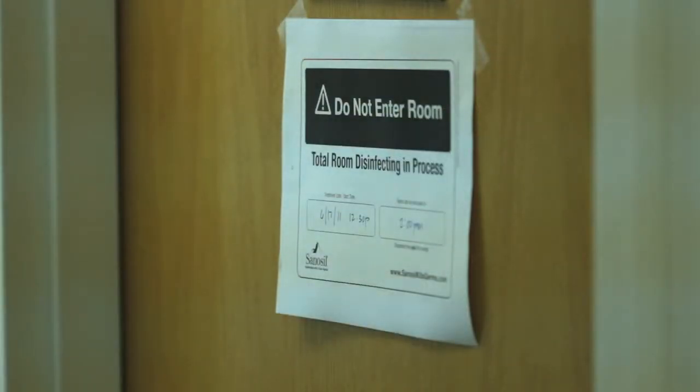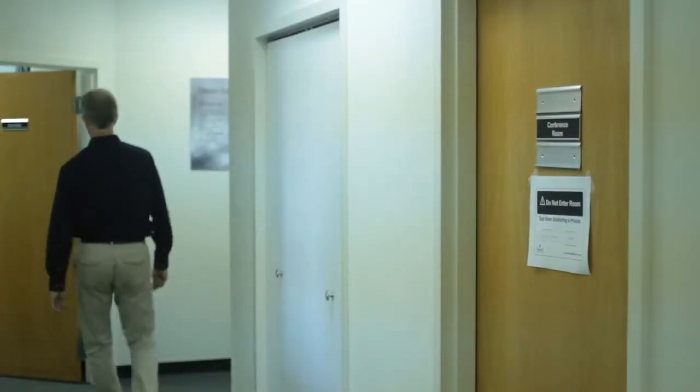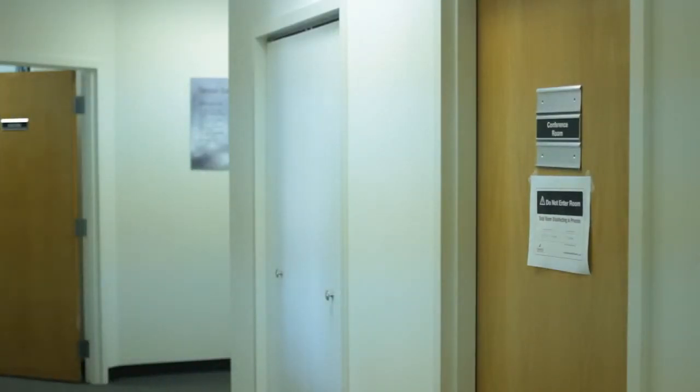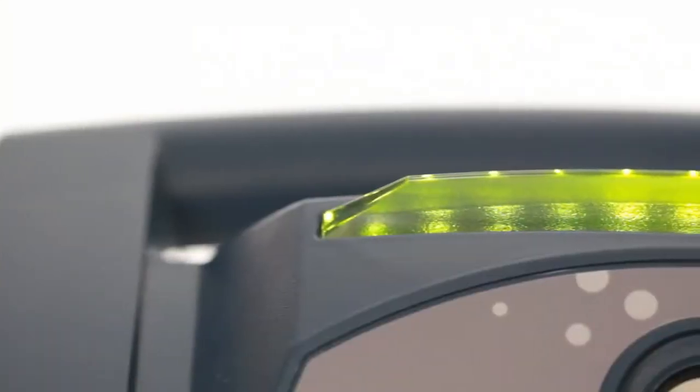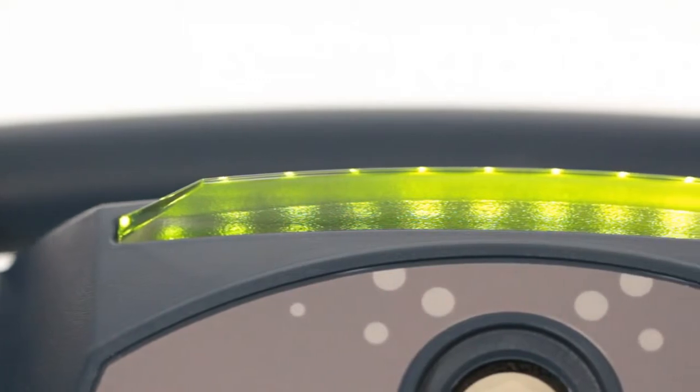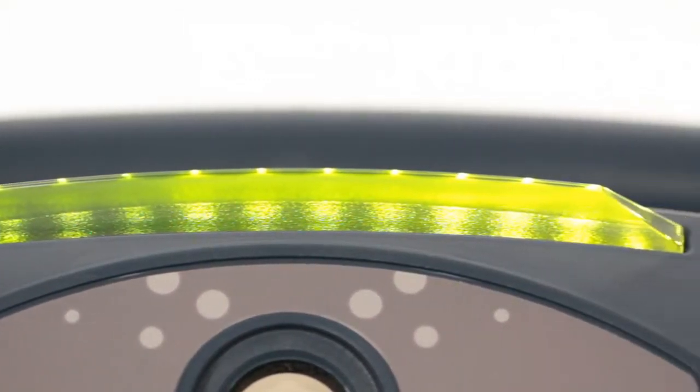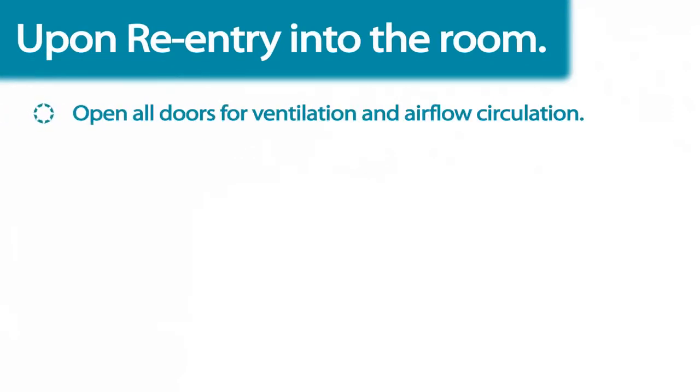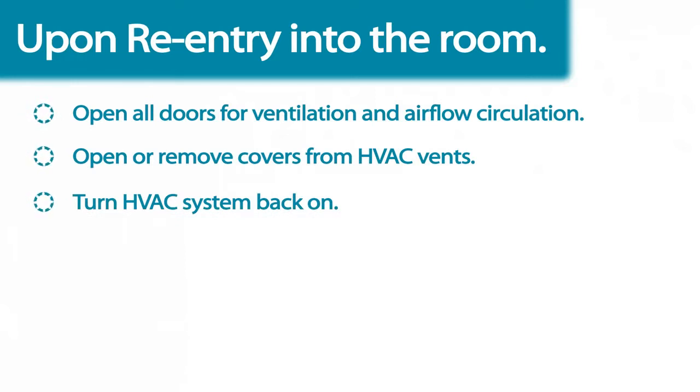When the Halo has finished dispensing, the room will be full of atomized Sanosil disinfectant and should not be entered. The status indicator will continue to illuminate a steady red. You may re-enter the room when the green status indicator light on the top of the fogger is illuminated. At this time, it is recommended that you open all doors to allow ventilation and airflow circulation in the room. Also, remove any covers from smoke detectors at this time.